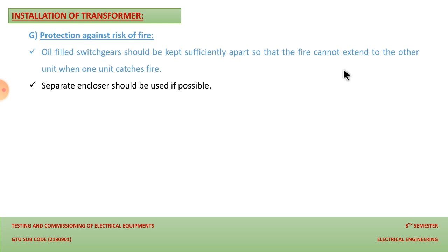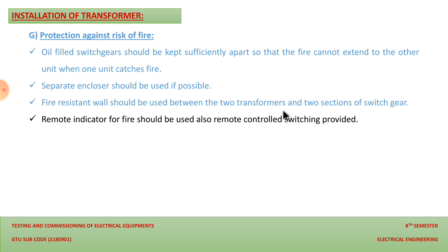And a fire resistance wall should be used between the two transformers and two sections of the switchgear. It is necessary because whenever fire is generated, we can protect our other utilities from the fire. So a fireproof wall should be provided between each utility. Then a remote indicator for fire should be used, and remote control switching also provided. This is for protection purposes. When we receive a fire, we can check the condition and operate our utilities from the remote end.